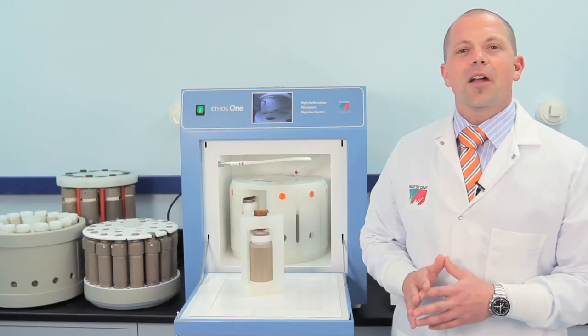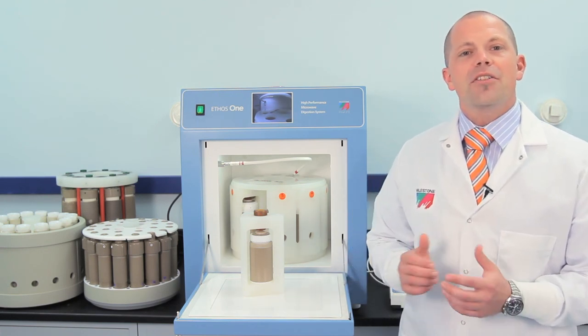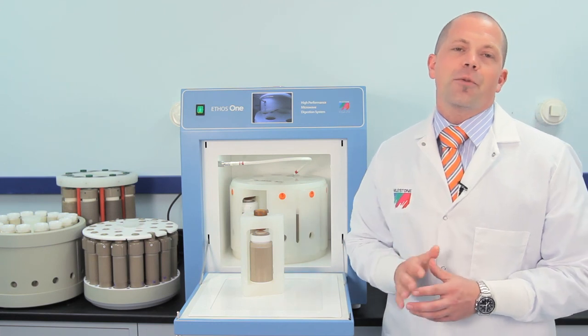The Ethos 1 comes standard with a thermocouple direct temperature probe which is the most accurate way to monitor temperature and ensure digestion runs are performed safely. Other options such as IR, pressure control, and pressure sensors are also available.